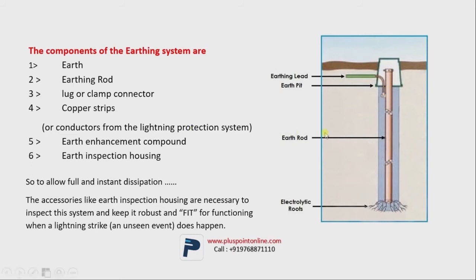If we talk about electrical earthing, then there's a copper wire attached to it. Other than these, there's a chemical compound, also known as earth compound, which keeps the rod and the earth gentle and also enhances the conductivity. The most important component is the earth inspection housing. The reason I'm focusing this much on this part is because it's the only place to check between the lightning protection system and the earthing. We can check from this if our earthing is proper or not. That's why it's so important for the earth inspection housing to be appropriate.